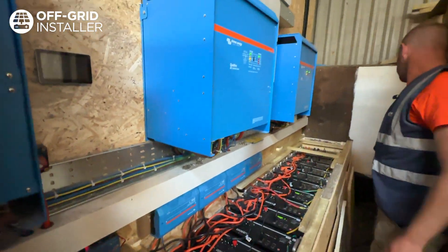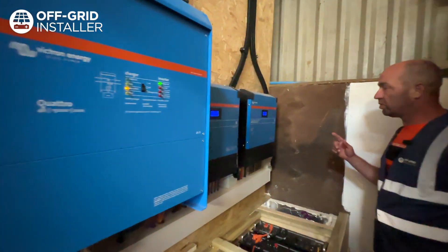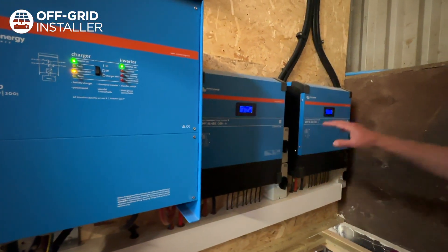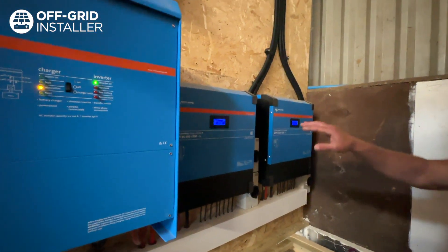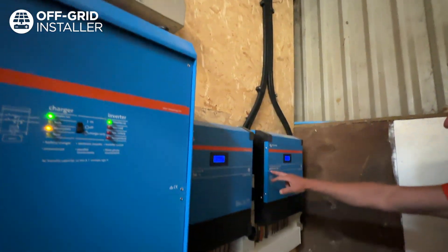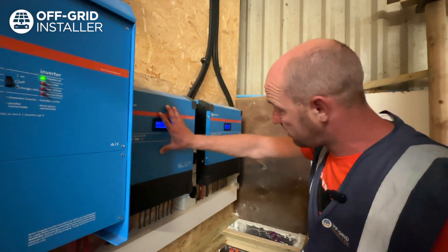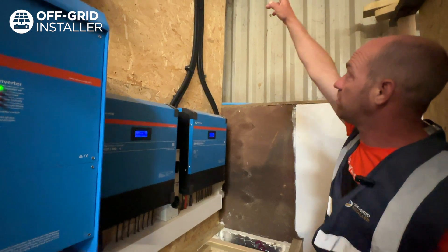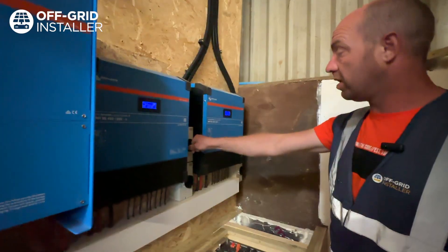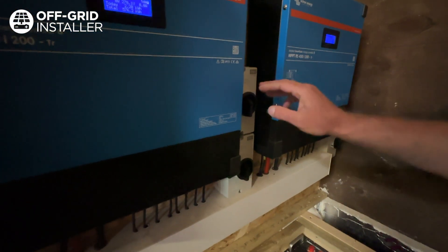Coming up from there at the end, we've got two RS450 200 amp solar charge controllers. Effectively, in each one of these there are four MPPT trackers — which stands for maximum power point tracker. So we've got eight solar charge regulators inside. You can see the cables come up off the roof, down through the flexi conduit, into the DC isolators. These are double pole, so effectively you're getting two strings of solar in each one.